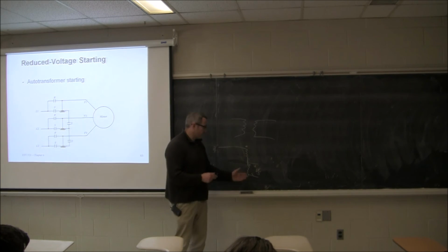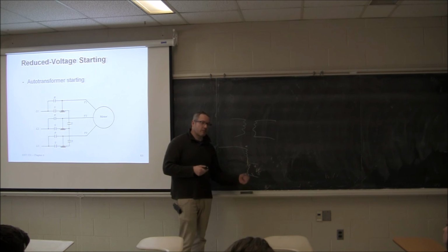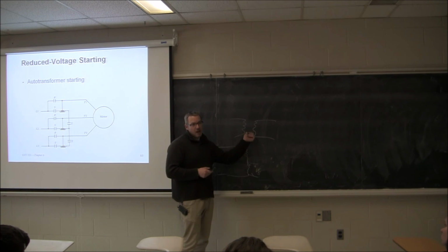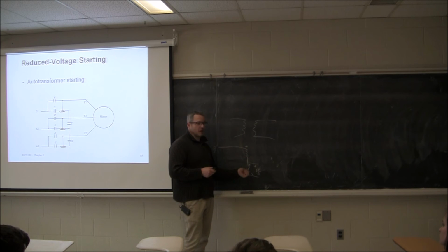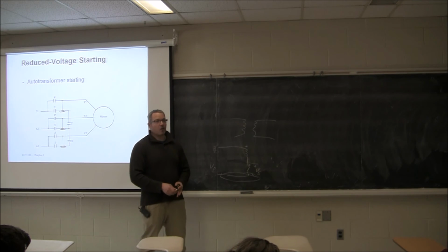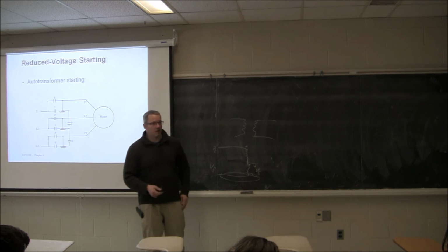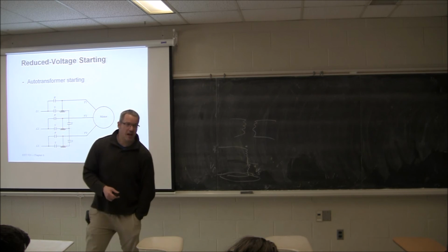Auto transformers, that's basically what they do. They increase or decrease the voltage. Sometimes I've seen them go 345 to 115 kV. So they're really good for just doing voltages, and they're really small as compared to, like here, to move a lot of power, has to be much, much greater than this one. But since this winding is common, you don't have to send all the power through that winding. You can share some of it. So that's how an auto transformer works. You literally just share the two.